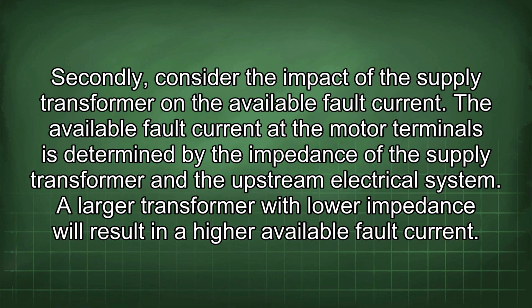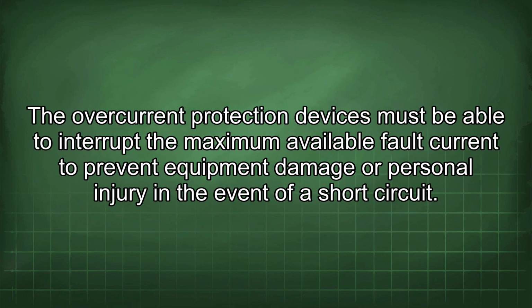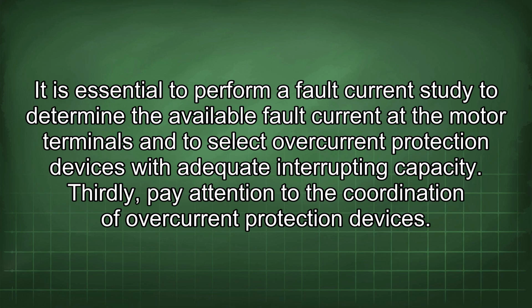Secondly, consider the impact of the supply transformer on the available fault current. The available fault current at the motor terminals is determined by the impedance of the supply transformer and the upstream electrical system. A larger transformer with lower impedance will result in a higher available fault current. The overcurrent protection devices must be able to interrupt the maximum available fault current to prevent equipment damage or personal injury in the event of a short circuit. It is essential to perform a fault current study to determine the available fault current at the motor terminals and to select overcurrent protection devices with adequate interrupting capacity.